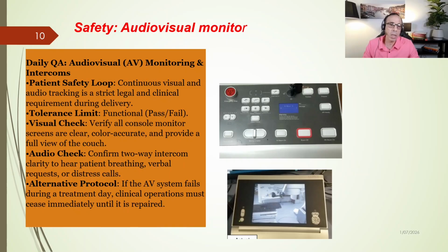During your morning QA, turn on the console screen and check every camera angle. You need to make sure that the picture is crystal clear, color accurate, and gives you a complete unobstructed view of the patient and the treatment couch. Next, test the two-way intercom. You need to be 100% sure you can hear everything inside the room clearly, whether it is a patient's breathing pattern, a verbal question, or a sudden call for help.